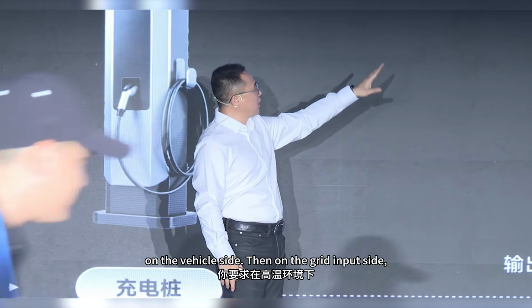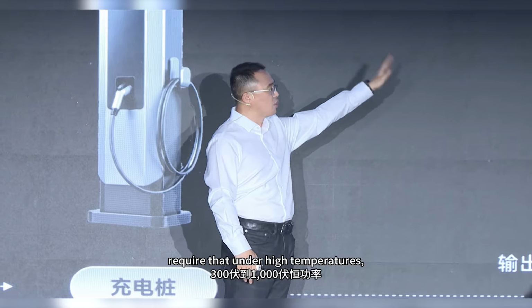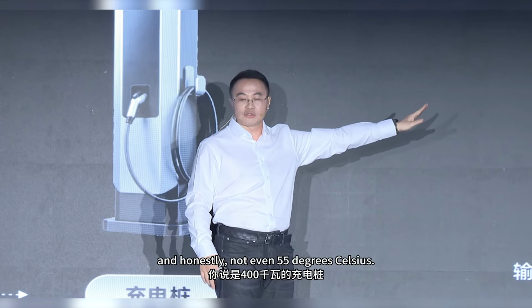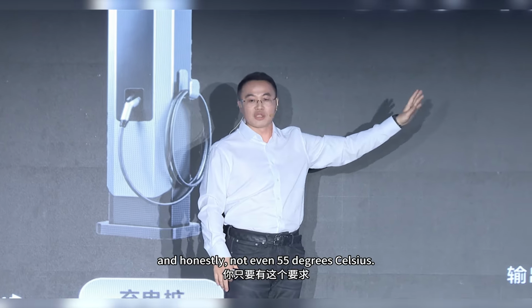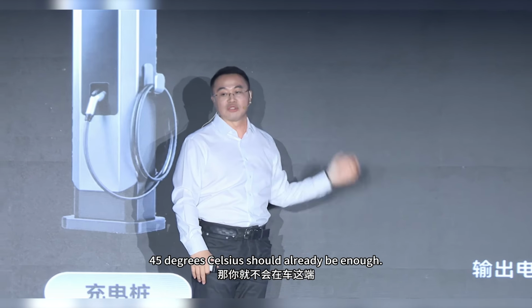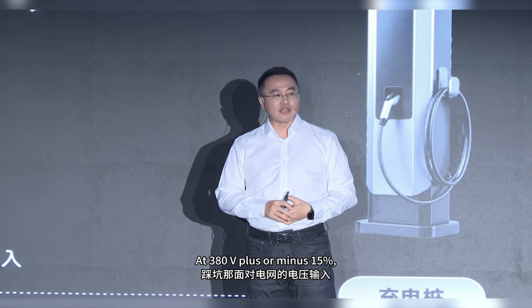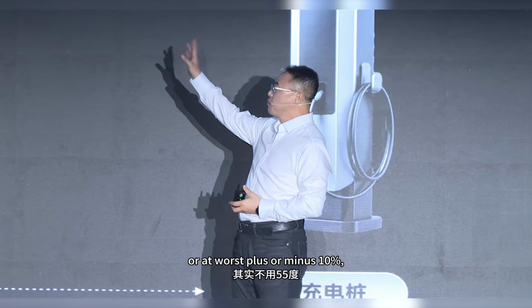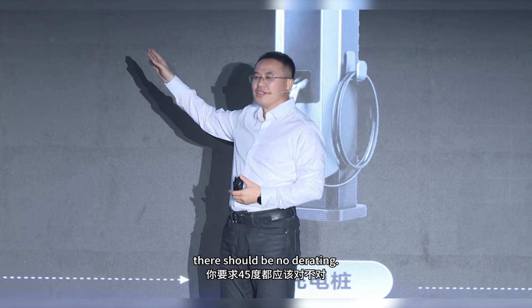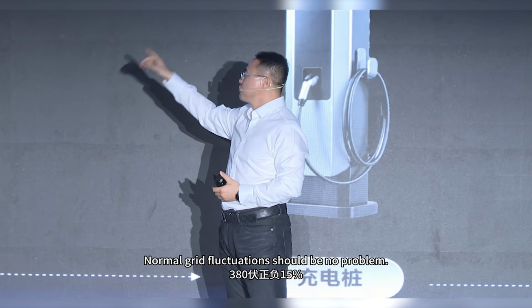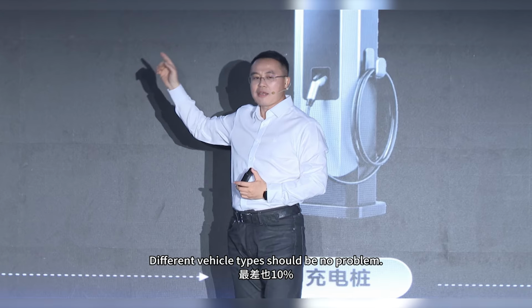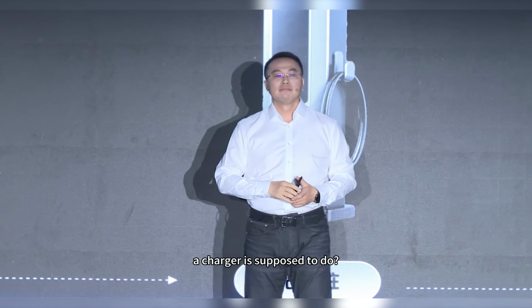On the vehicle side, then on the grid input side, require that under high temperatures—honestly, not even 55 degrees Celsius, 45 degrees Celsius should already be enough—at 380 volts plus or minus 15%, or at worst plus or minus 10%, there should be no derating. Normal grid fluctuations should be no problem. Different vehicle types should be no problem. Is this not simply what a charger is supposed to do?